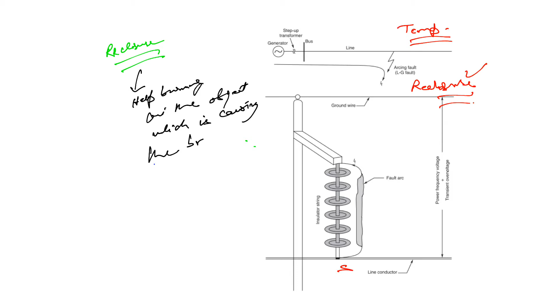Generally, three reclosures are attempted in a low voltage system, after which the breaker is locked out. However, in an extra high voltage system, where the damage due to the short circuit is very high and system stability is at stake, and also the equipment is very costly, only one reclosure is allowed. And this reclosing is actually done automatically.